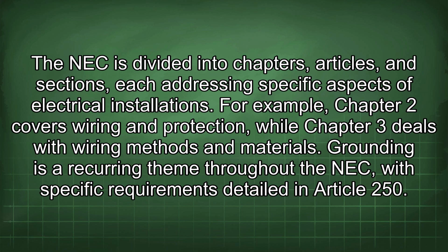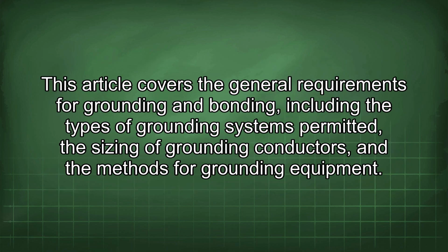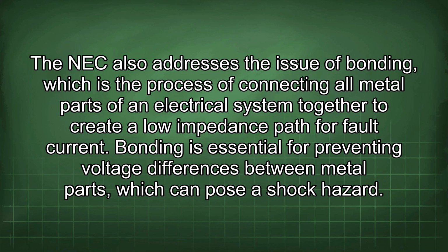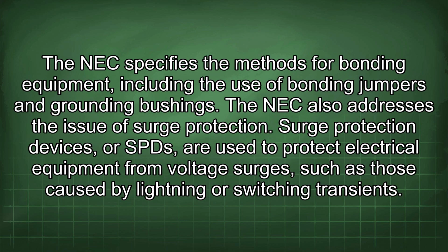Grounding is a recurring theme throughout the NEC, with specific requirements detailed in Article 250. This article covers the general requirements for grounding and bonding, including the types of grounding systems permitted, the sizing of grounding conductors, and the methods for grounding equipment. The NEC also addresses the issue of bonding, which is the process of connecting all metal parts of an electrical system together to create a low impedance path for fault current. Bonding is essential for preventing voltage differences between metal parts, which can pose a shock hazard. The NEC specifies the methods for bonding equipment, including the use of bonding jumpers and grounding bushings.